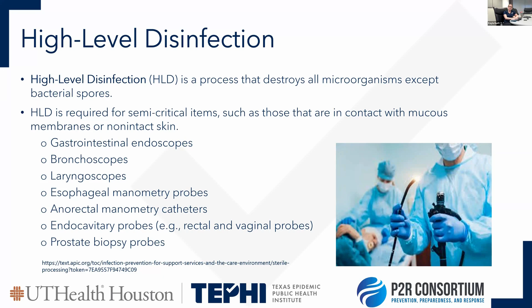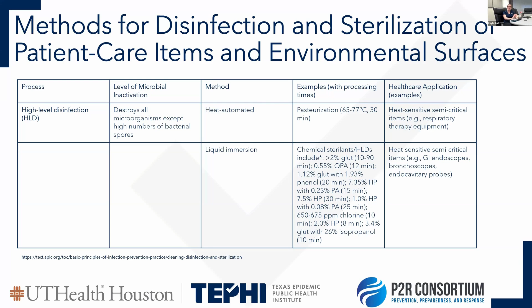The two main methods used in high-level disinfection are heat automation and liquid immersion. And depending on your type of equipment and what the manufacturer instructions for use, or MIFU, says, you'll be using different methods to make sure that you're processing it with a certain time and temperature for that cycle for that specific piece of equipment. And these devices that usually have high-level disinfection are very sensitive to heat, so that's why they can't be sterilized. So make sure that these items never go through sterilization, that they're specifically for high-level disinfection processes.